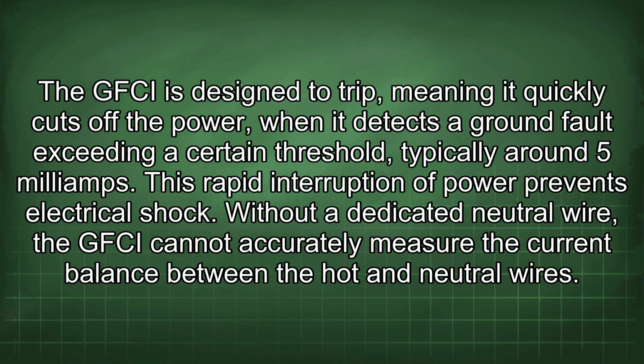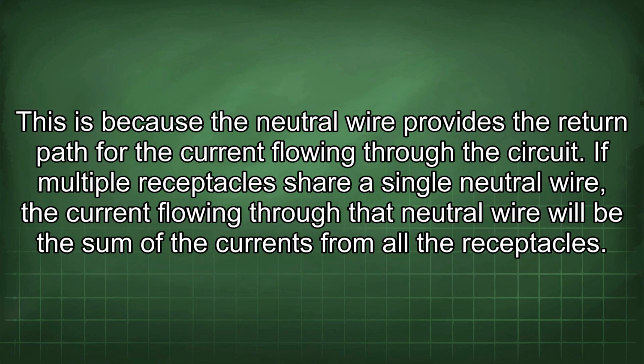This leakage current is called a ground fault. The GFCI is designed to trip, meaning it quickly cuts off the power when it detects a ground fault exceeding a certain threshold, typically around 5 mA. This rapid interruption of power prevents electrical shock. Without a dedicated neutral wire, the GFCI cannot accurately measure the current balance between the hot and neutral wires. This is because the neutral wire provides the return path for the current flowing through the circuit.